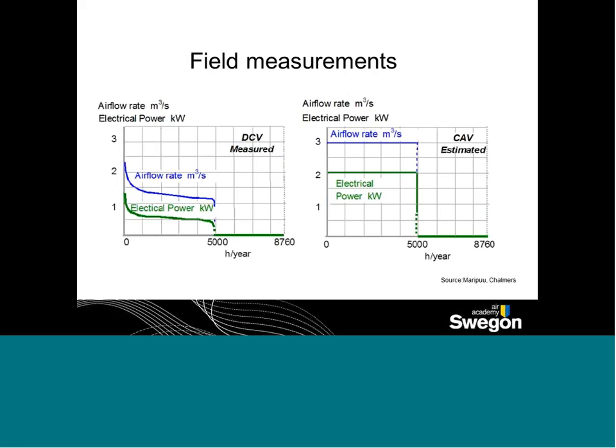Looking at some field measurement data, on the left is a building measured for the whole year. Of course it wasn't occupied all the time, and you can see how the electrical power and airflow rates — how much of the time you had higher airflow and higher electrical power consumption — how that tailed off. These are actual measured values from the building, compared to a CAV system where you'd have to make sure you covered peak demands all the time. Even so, there is significant energy to be saved.